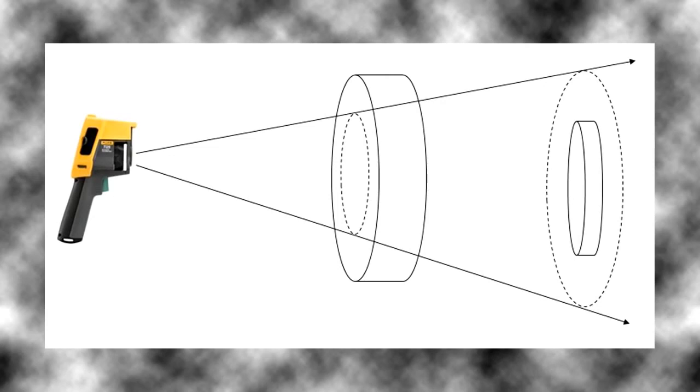In the second case, the target is smaller than the spot size and any temperatures that are in that area will be averaged in with the temperature of the target.